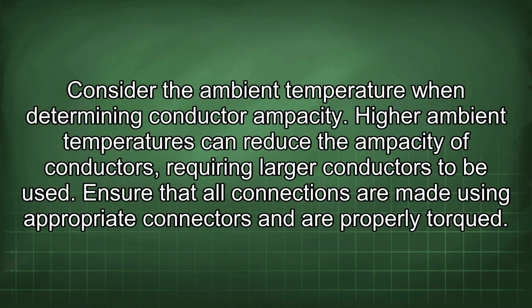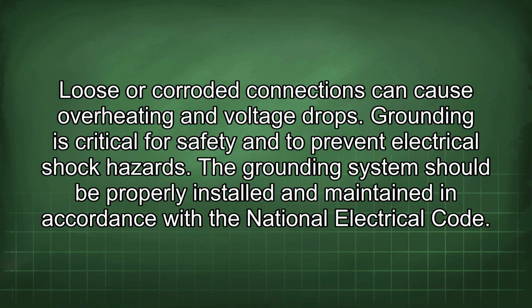Consider the ambient temperature when determining conductor ampacity. Higher ambient temperatures can reduce the ampacity of conductors, requiring larger conductors to be used. Ensure that all connections are made using appropriate connectors and are properly torqued. Loose or corroded connections can cause overheating and voltage drops. Grounding is critical for safety and to prevent electrical shock hazards. The grounding system should be properly installed and maintained in accordance with the National Electrical Code.